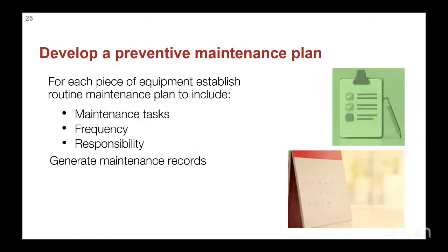Develop a preventive maintenance plan, the PM, for each equipment. For each piece of equipment, you need to establish the routine maintenance plan and have it. The maintenance task, the frequency, the responsibility, and generate maintenance records.